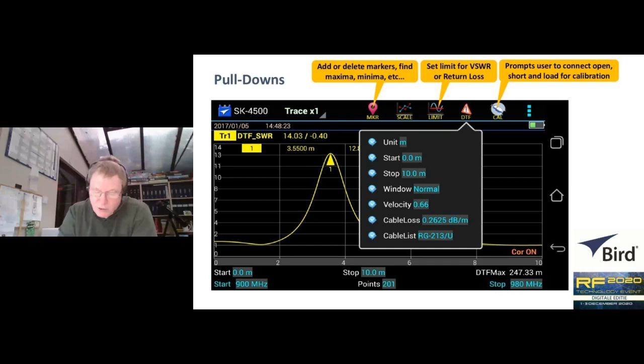Use of the pull-down is also a user-friendly mechanism for calibrating the instrument. Can you see there, top right-hand corner of the screen, cal? That's another pull-down. A frequency domain reflectometer should ideally be calibrated every time we change the range of operating frequencies, or when the instrument encounters a significant change in ambient temperature. The calibration procedure involves connecting first a precision open circuit, then a precision short circuit, and finally a precision 50 ohm load to the test port. The pull-down menu for the calibration prompts us through each of these various actions and tells us when each stage is complete. Finally, when the instrument has been calibrated for that range of frequencies, the words correction on, or COR on, appear at the bottom right-hand corner of the display. You can see it there in red.